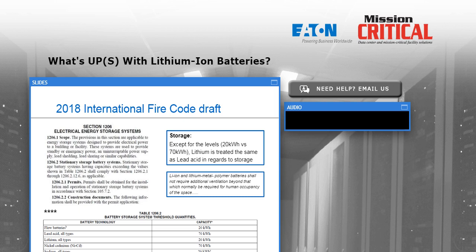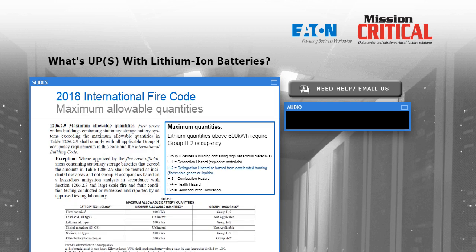At the bottom of the slide, you see the capacity is listed in kilowatt hours. That's a little different than we're traditionally used to thinking of battery capacity, but it does apply to all the different types of battery chemistry - valve-regulated, lead-acid, NiCads, lithium, and others. There are capacity levels at which the fire code requirements may change, especially in large installations, and I think the next slide will show us that.